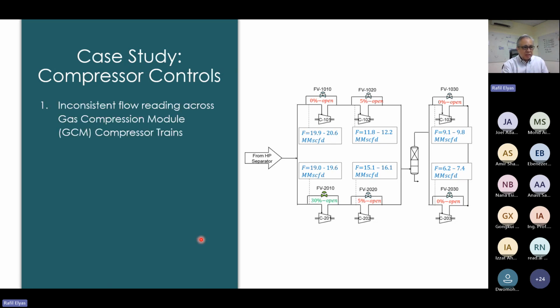What was happening is this is a gas compression module. It's essentially two parallel trains, each with 3 stages: low pressure, intermediate pressure, combine back, go through a glycol dehy, and then into the third stage. This will be going into gas injection and gas lift. One of the problems they had was inconsistent readings for some of these compression trains. You can see that the flows over here seem imbalanced. You've got more flow in one, less flow in another, and the flow rate readings were all over the place. So the flows were maldistributed across the compression trains.